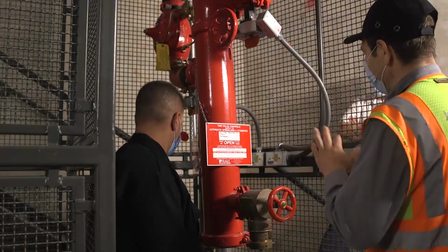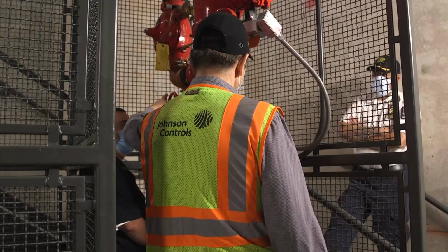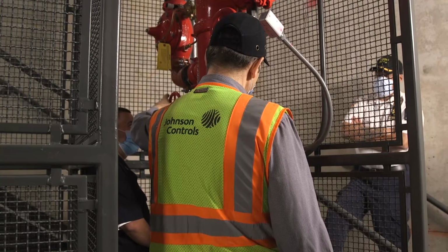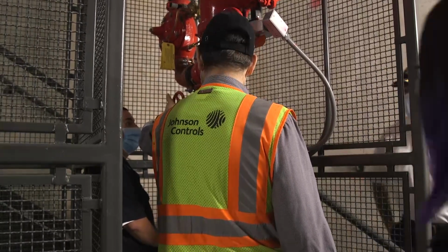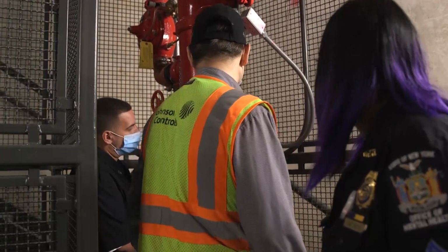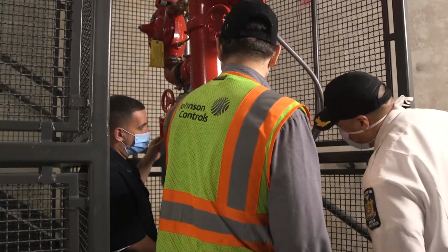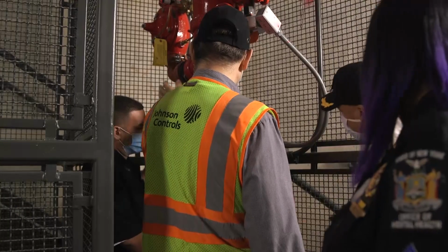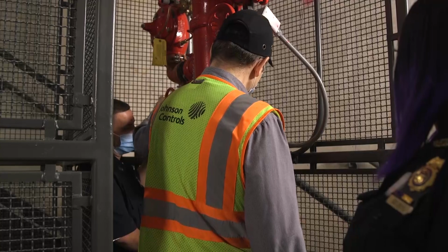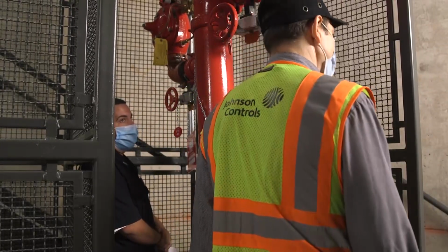So first, once you make sure everything is good, you slowly open the valve until some kind of resistance, not too much, a little bit of resistance, and you see the light is just blinking, not steady anymore. That means it's normal. So now this is how you can see the difference without going to the panel. When it's closed, the light is steady. When it's open, it's back to blinking. So it needs to be blinking. Yeah, the blinking is a normal state.